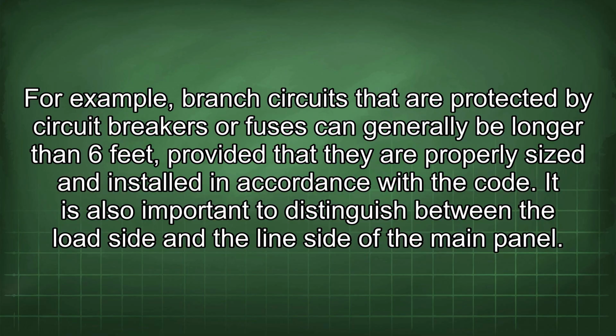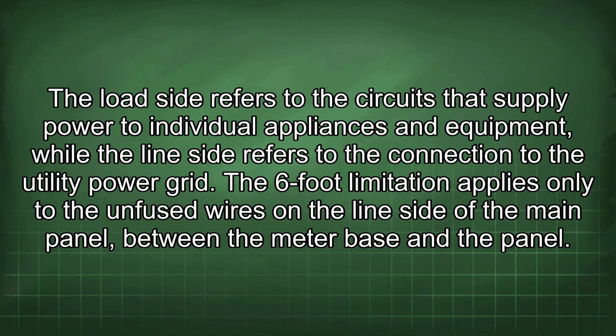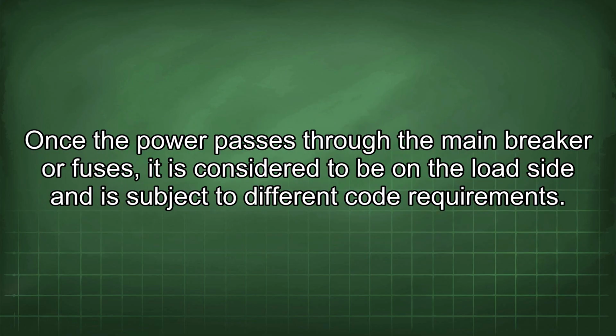It is also important to distinguish between the load side and the line side of the main panel. The load side refers to the circuits that supply power to individual appliances and equipment, while the line side refers to the connection to the utility power grid. The 6-foot limitation applies only to the unfused wires on the line side of the main panel, between the meter base and the panel. Once the power passes through the main breaker or fuses, it is considered to be on the load side and is subject to different code requirements.